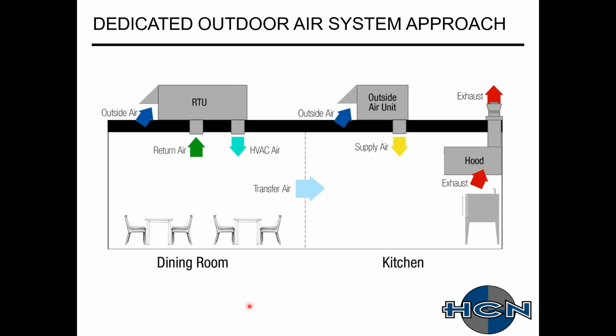the ASHRAE handbook, maximizing on transfer air. So really looking at 90.1, using about 50% of that air in the design. You have the rest of the kitchen and the dining space that you guys are worrying about. Utilize that because you're already heating and cooling that air. Bring in a little bit more outside air for that. Use that transfer air, and then also size up an outside air unit for the makeup air.